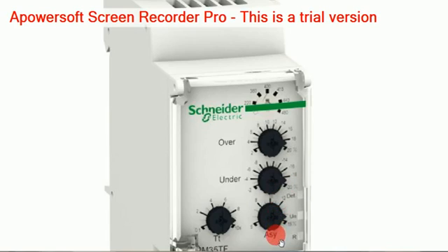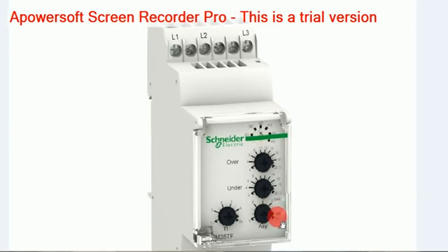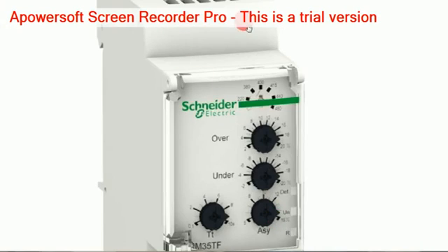Then there is the asymmetry knob, which is very important for adjustment. This asymmetry knob compares the 3 voltages — R, Y, and B — and adjusts to determine whether to switch on the relays. The 4th knob is for timing — how much time to switch on. This goes from 0.1 seconds up to 10 seconds.